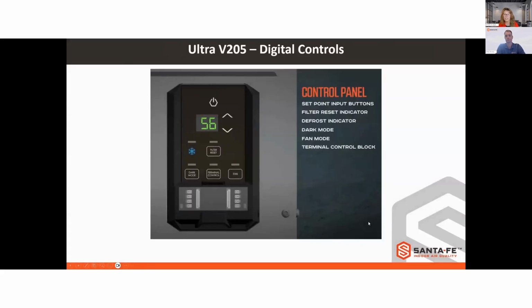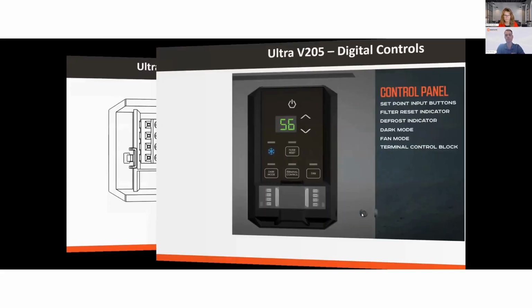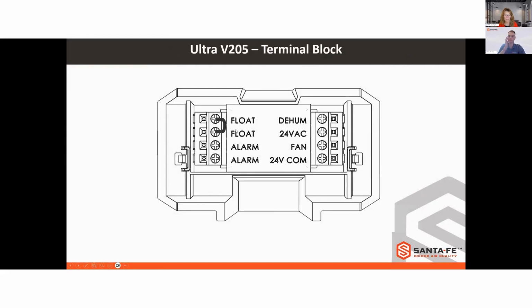So this unit does have a digital control also. It is different than the one on the V100, 125, and 155. This control is digital, so you can actually set the RH directly on this. It does have a defrost indicator, and dark mode, if you don't want that RH level to illuminate. We've got a fan mode, and again, this one does have a terminal block on it as well. And that's what this terminal block would look like. So again, we've got the float here, and we are able to wire a motorized damper for our ventilation strategy directly to the dehumidifier.